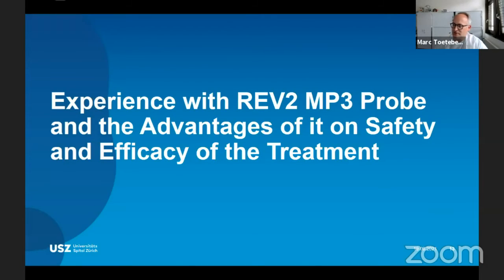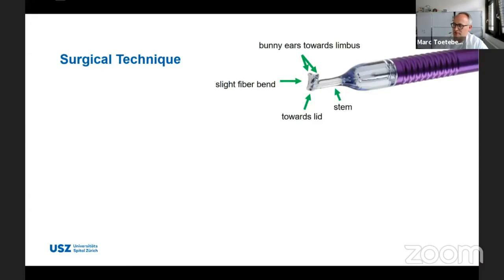My experience with the new REV2 MP3 probe, so the new hand probe, the advantages and the safety on that. First of all, if you look at it, the very big difference you have is the long and thin stem, the foot plate, which is slightly bent and curved. You have the bunny ears on one side that go towards the limbus, and the other side, which is flat, goes towards the lid. You do not need a speculum if you use the MP3 hand probe, the REV2.